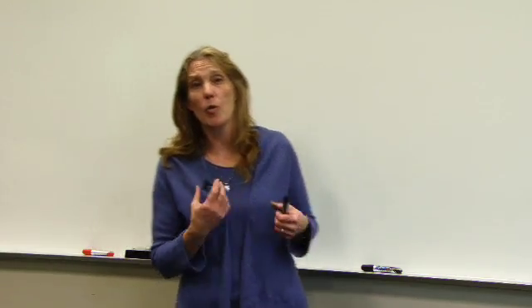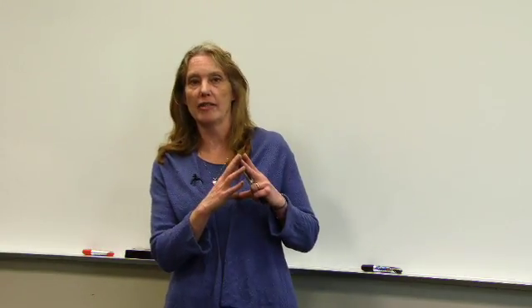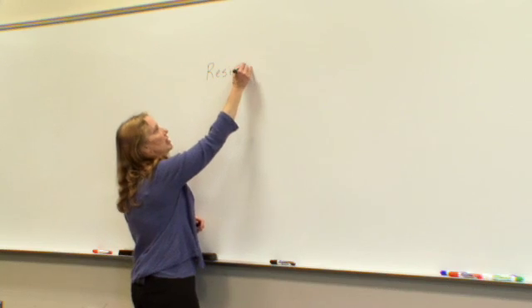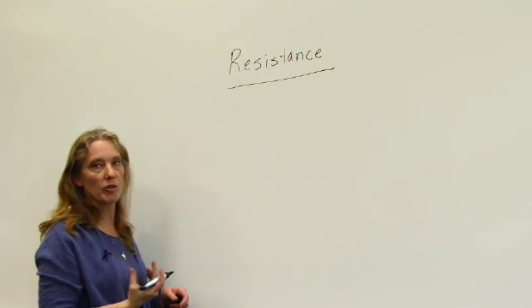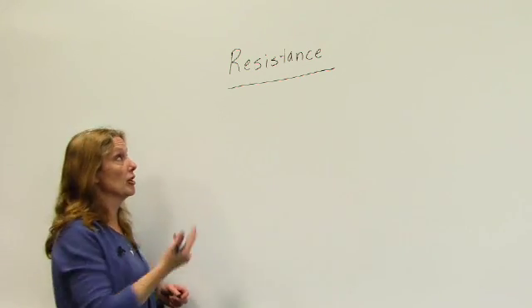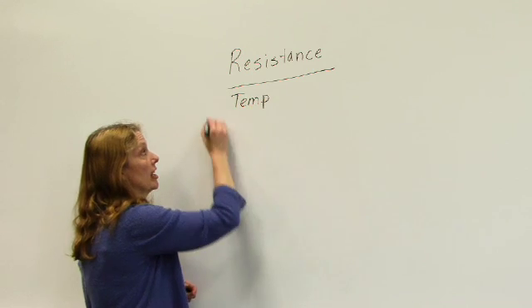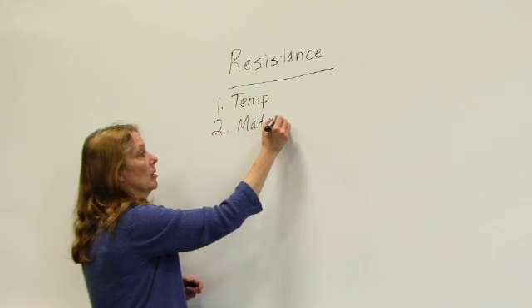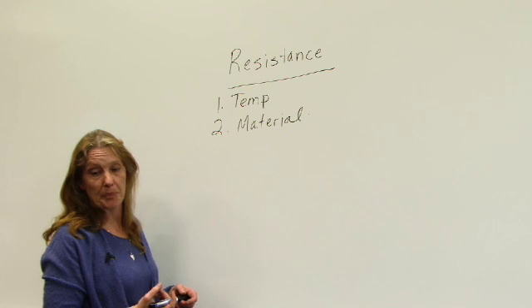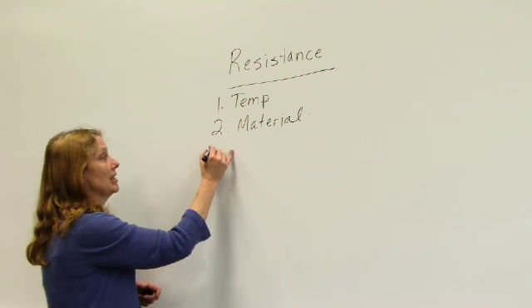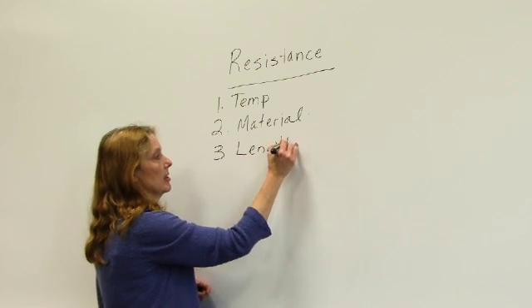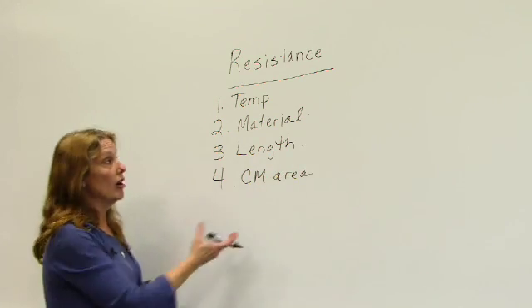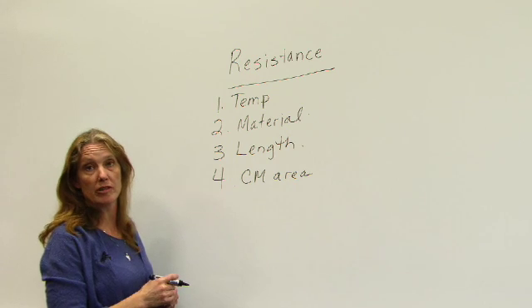So the first thing we want to talk about is when we talk about our wire resistance, we have to look at the actual size of the wire. Now remember, resistance of a conductor is dependent upon four different things: temperature, ambient temperature of the area; material, most common conductors are aluminum or copper; length of the conductor; and our circular mil area or the area of the conductor. All these four factors determine how much resistance I have in my conductor.